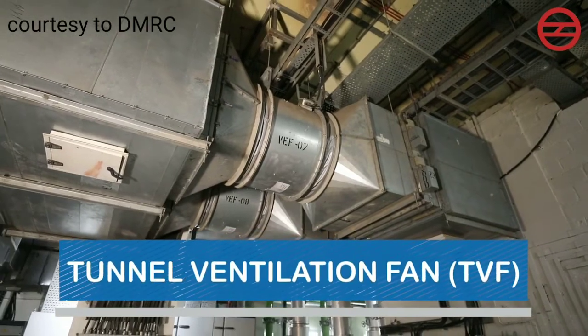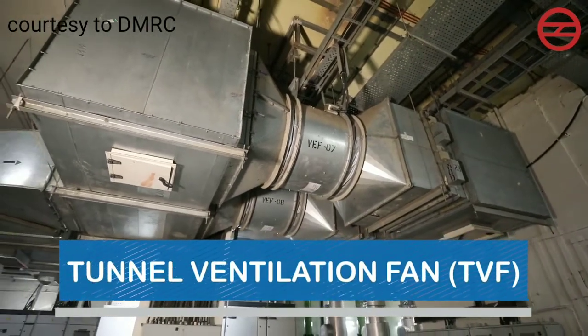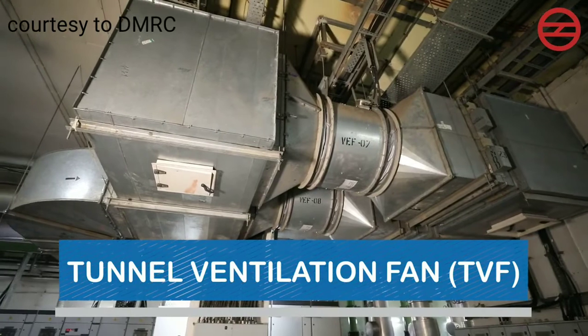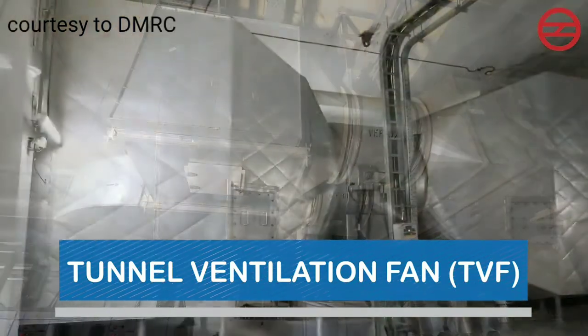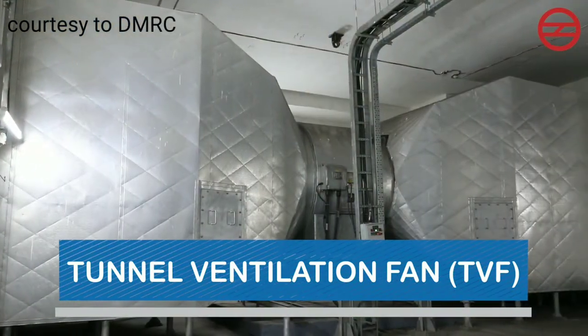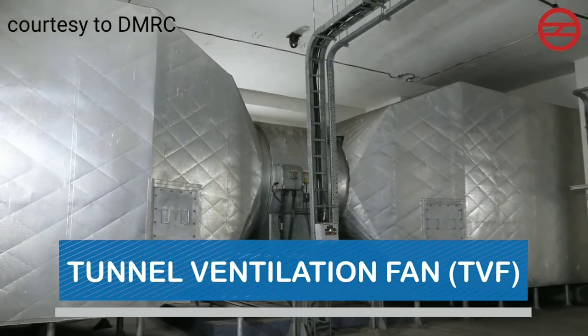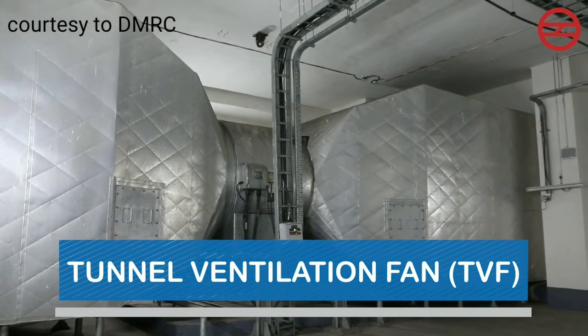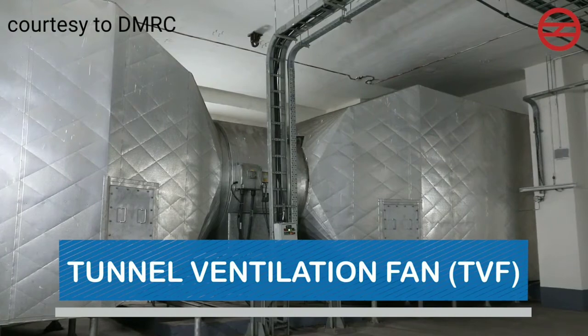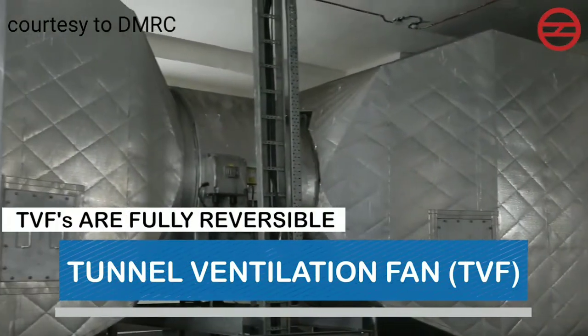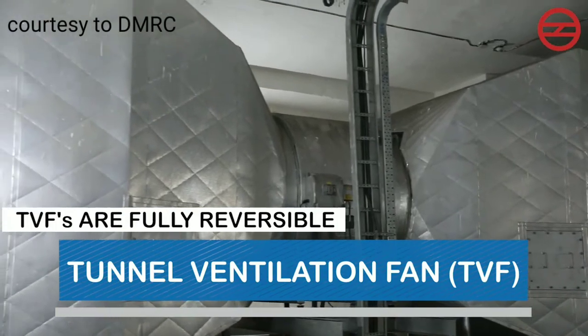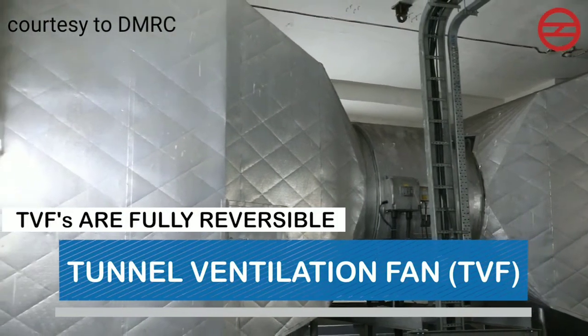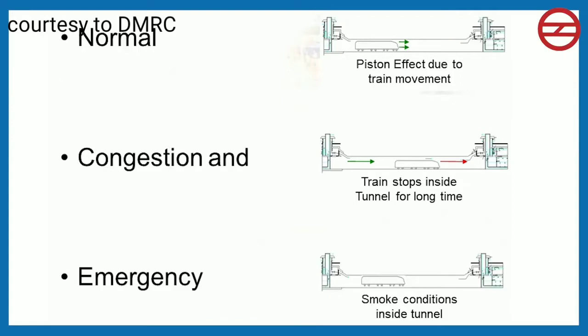Now, in this system, the fans work in combination. That is, in case of any critical situation inside tunnel, fan at one end of the tunnel will work in supply mode and push the fresh air inside tunnel, whereas the fan at the other end will work in extract mode and pull the air from the tunnel. Therefore, these tunnel ventilation fans are fully reversible. There are 3 modes of operation of TVS: normal, congestion, and emergency.